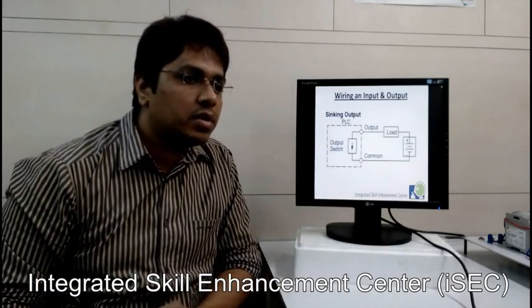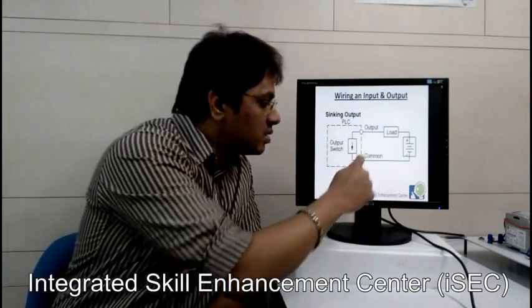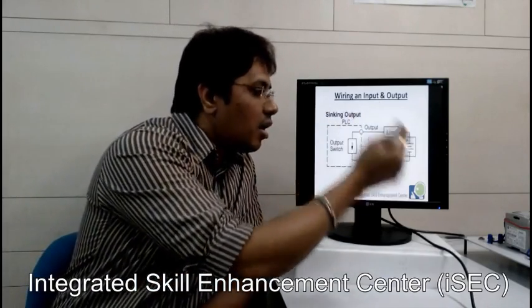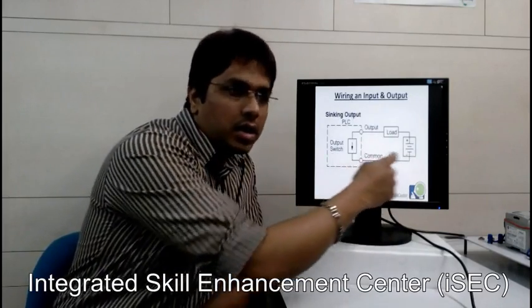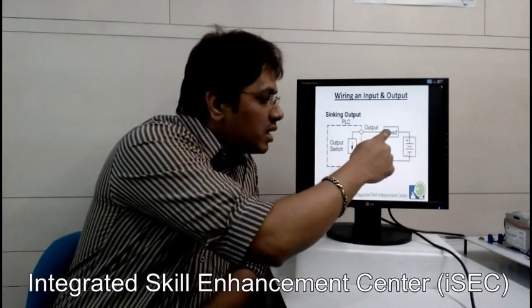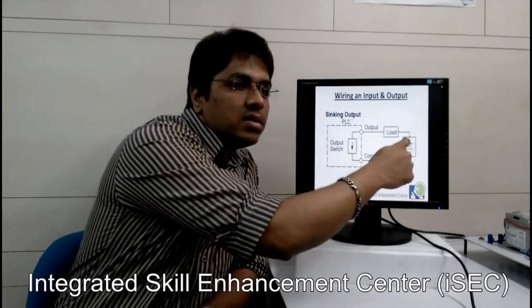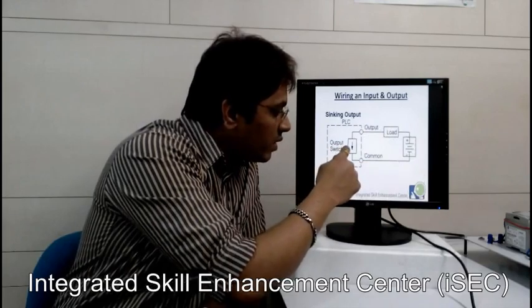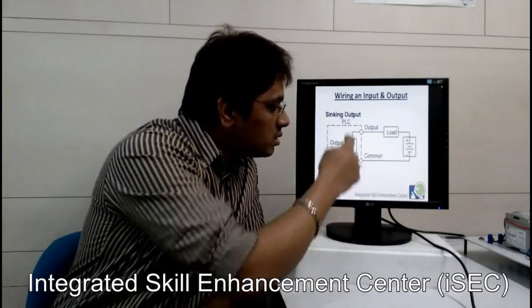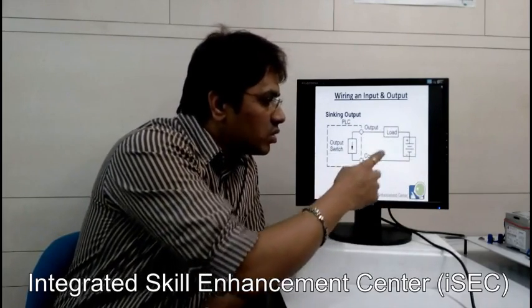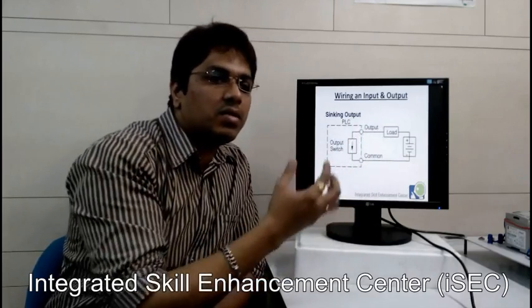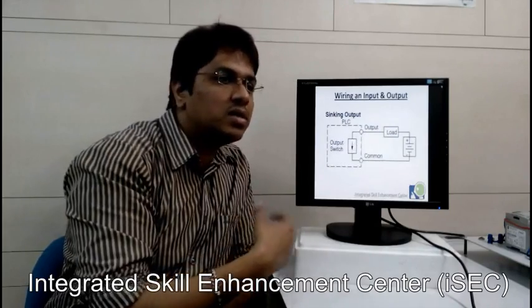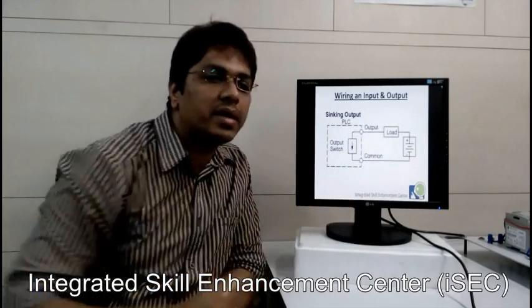Now what is sinking output? When you connect a PLC as a sinking output, the common will again be ground. The output is connected to the load, and that is connected to the VCC of the power supply. Whenever the output conducts, the PLC will take current from the output device — this is called a sinking output manner.